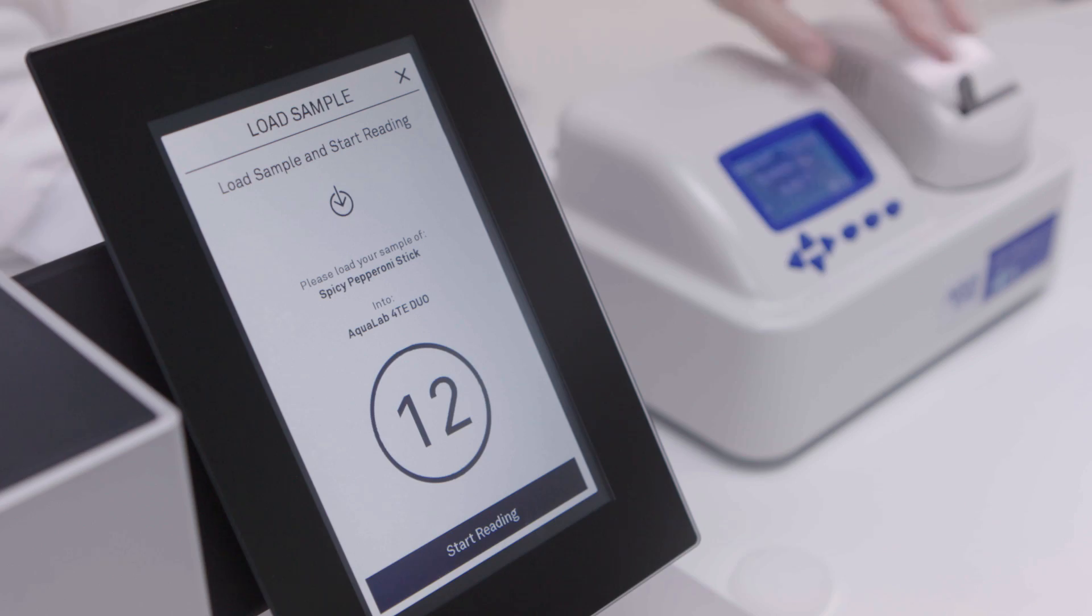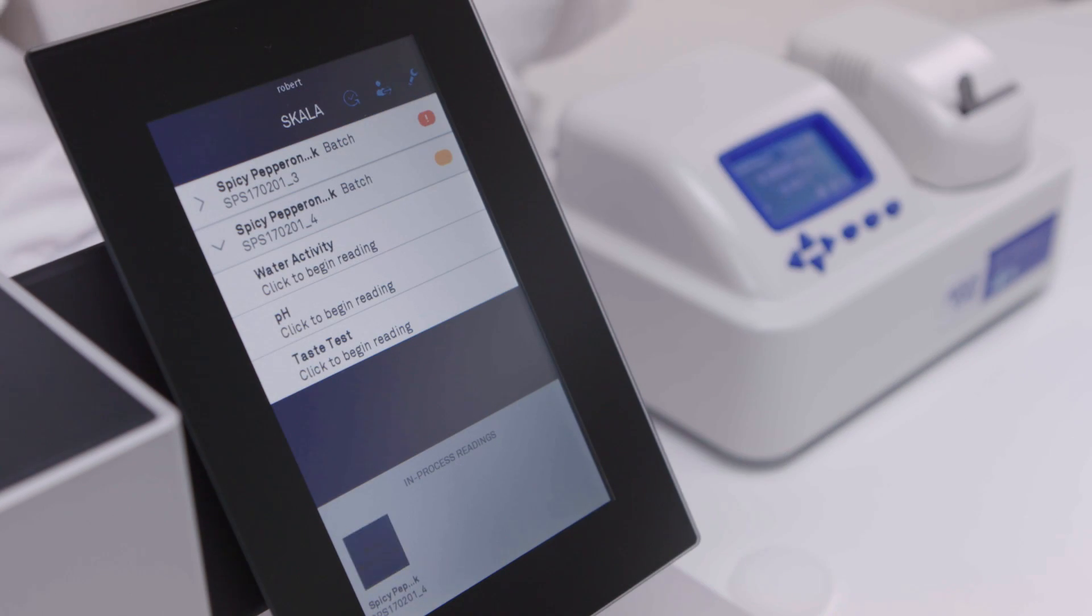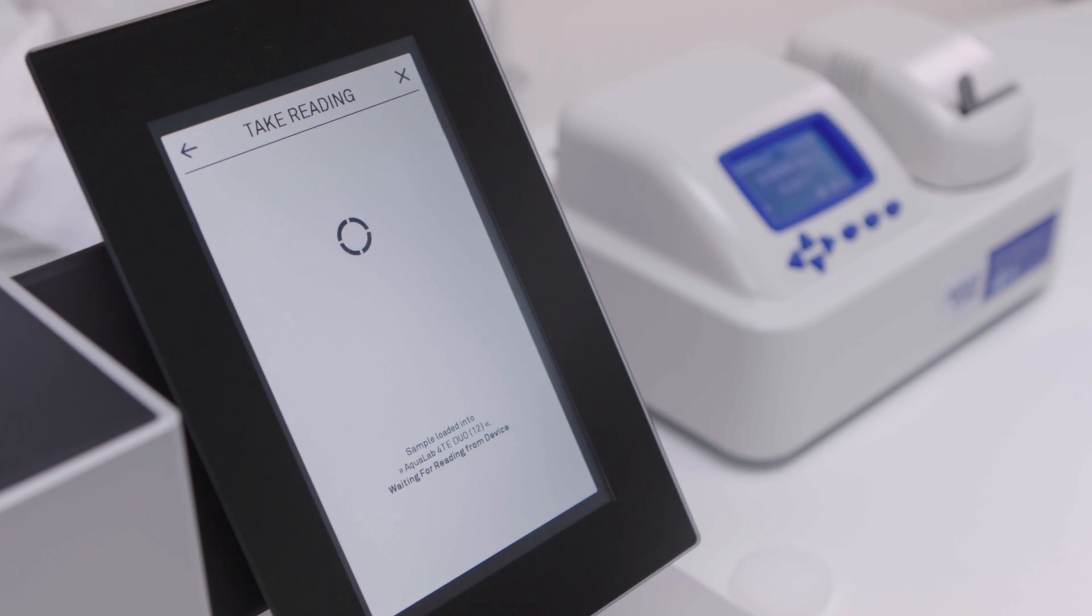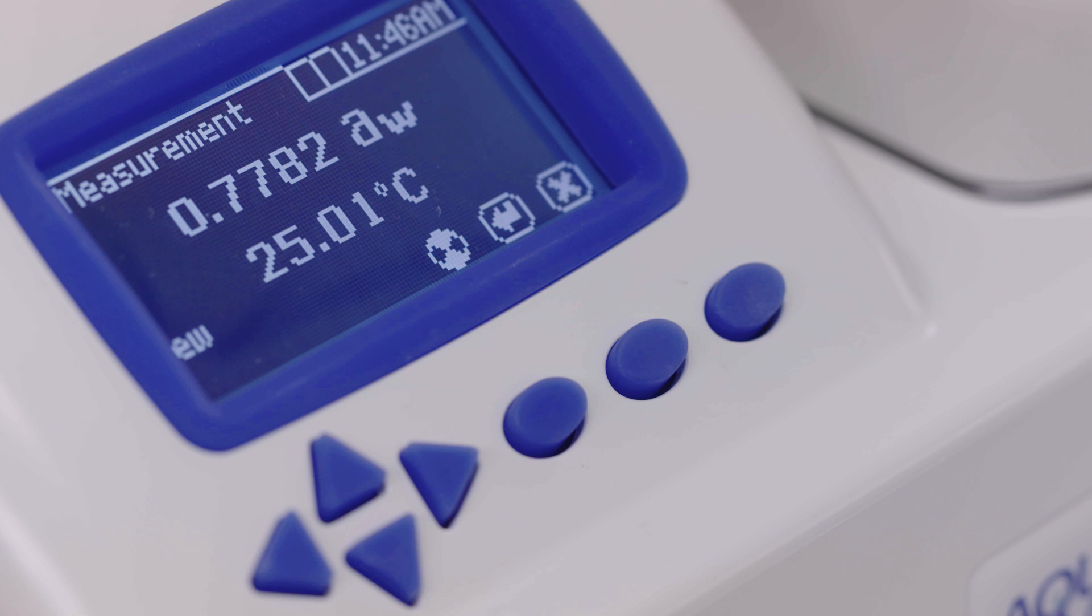In one or two minutes, a preliminary number will show. The spinning wheel at the bottom of the screen indicates the Aqualab is still checking to see if the sample has stabilized. If you are recording readings manually, you can listen for the beep that shows that the instrument is done. Your final water activity reading will show on the screen.